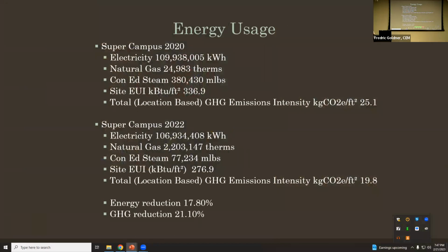pipe rupture. Now, I'm just comparing 2020 to 2022. You can see the electricity usage, gas usage, and steam usage in 2020, and we were at 336 kBTUs per square foot at that point. In 2022, after the steam boiler plant came online, steam was reduced by 80%. We still need steam for steam turbines and our process loads, but we're using only 20% of that, and of that 20%, 10% is being used just to keep our pipes hot. Overall, between 2022 and 2020, our energy usage was reduced by 17.8% and our GHG reduction was 21.1%. That's using ESPM, Energy Star Portfolio Manager data.